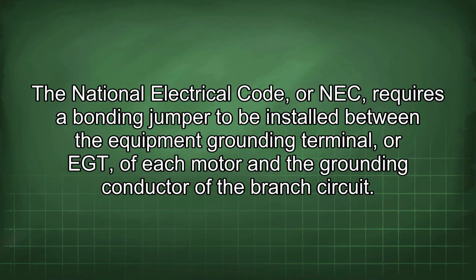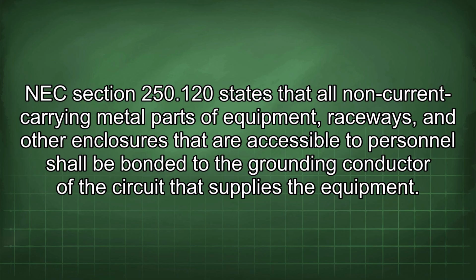The National Electrical Code (NEC) requires a bonding jumper to be installed between the equipment grounding terminal, or EGT, of each motor and the grounding conductor of the branch circuit. NEC Section 250.120 states that all non-current carrying metal parts of equipment, raceways, and other enclosures that are accessible to personnel shall be bonded to the grounding conductor of the circuit that supplies the equipment.